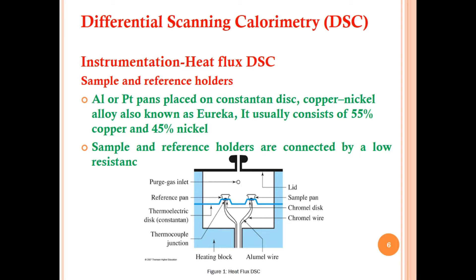Aluminum pans are placed on a constantan disc, a copper-nickel alloy also known as Eureka, consisting of 55% copper and 45% nickel. Sample and reference holders are connected by low resistance. The block diagram shows a lid covering the whole furnace system, the sample pan, chromel disc, chromel wire, and alumel wire.